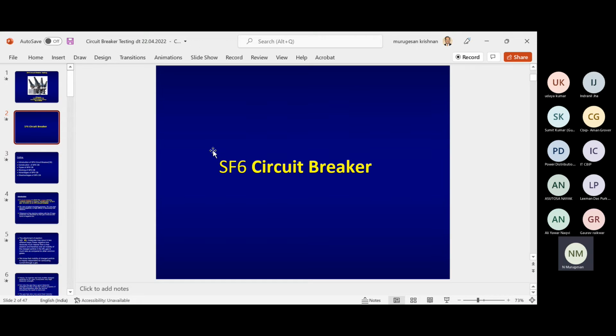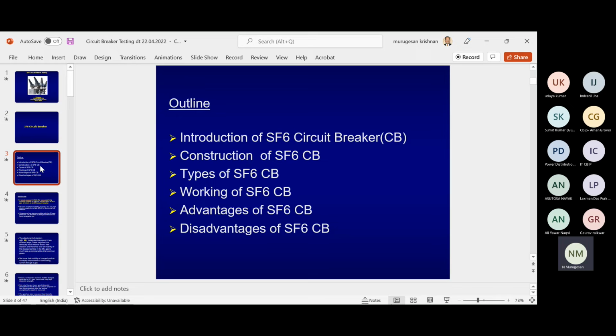So that has to be increased. So that medium is air. When you use air to increase the length of the arc, it is called an air circuit breaker. When you use SF6 as the medium, it has high insulation capacity. As soon as the contact is open, the SF6 comes in between the two contacts. So this is a high resistance medium, a high insulation strength medium. When a high insulation medium is introduced between the contacts, the arc becomes small. The resistance is high, so the current will come down. So friends, this is what we are going to do. But SF6 is a greenhouse gas. You know that, no? Are you aware?